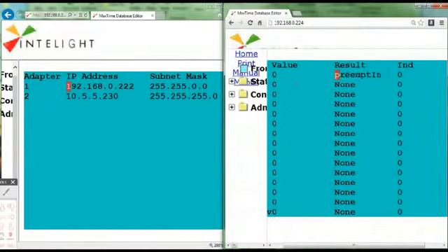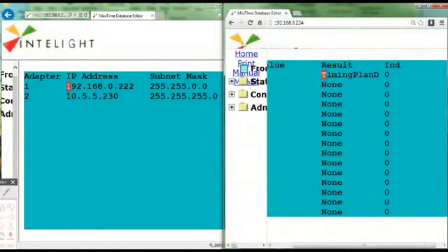inputs to the controller. It could be a preempt, an omit, a phase plan, a detector. Basically, any input into the controller can be activated from this peer control. And of course, I have to scroll down quite far to find my pattern control. So when I get down a little bit further, timing plans, I'm going to go to timing plan D. When I go to timing plan D, I need a pattern number. I'm going to put 11 in.